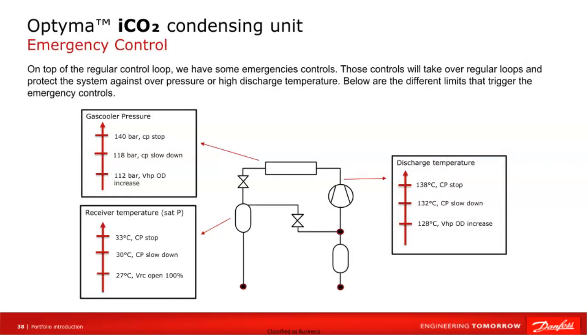In addition to the standard control loops, we have implemented emergency safeguards that take over control in the event of extreme conditions. Below, we present the limit values at which these protections come into operation. Regarding protection against excessive pressure in the gas cooler, when the pressure exceeds 112 bar, the high pressure valve gradually increases its opening to reduce the pressure. When the pressure reaches 118 bar, the compressor automatically reduces its speed. If the pressure exceeds 140 bar, the compressor will be completely turned off.